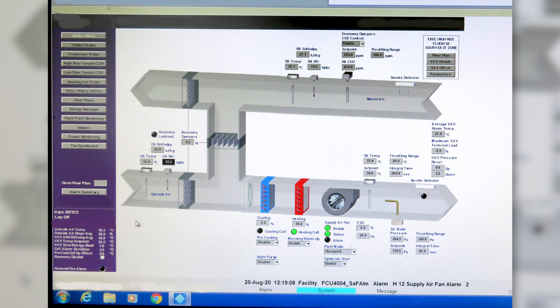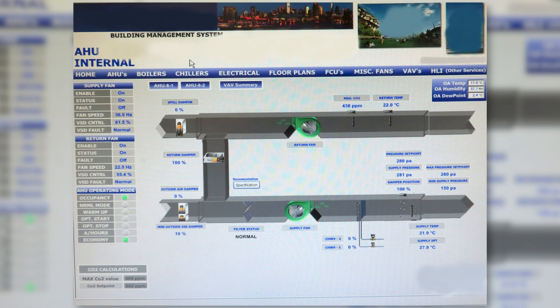In the second example, I think this is an old Honeywell BMS - really old graphic. But again it looks quite similar: dampers on the left, supply fan, heating and cooling coils, supply temperature and pressure controls. A bit more detail around a supply air pressure reset strategy, return air enthalpy and outside air enthalpy as part of economy cycle control. But the look of that graphic and how you see it is very similar to what we do nowadays.